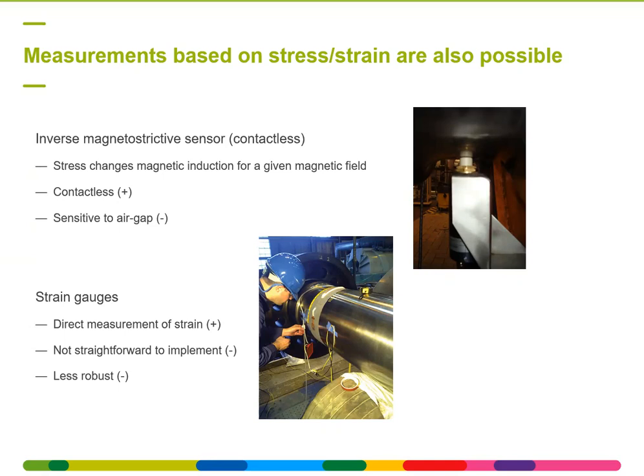The advantage, of course, is there. It's a direct measurement of stress strain, but it's sensitive to these air gap differences. Below you see strain gauges, a typical example of a direct measurement of strain, but it's less straightforward to implement and it's less robust in the long term, so it's not typically used.